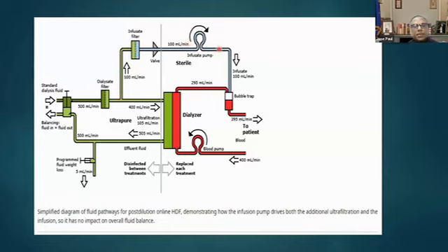Then there is an infusate pump, and part of the ultra pure water that is generated goes into the hemodiafilter, where it is used for dialysis, and the blood is taken from the patient's body. It goes through the blood pump and runs through the dialyzer. Then the infusate is infused back into the patient's blood.